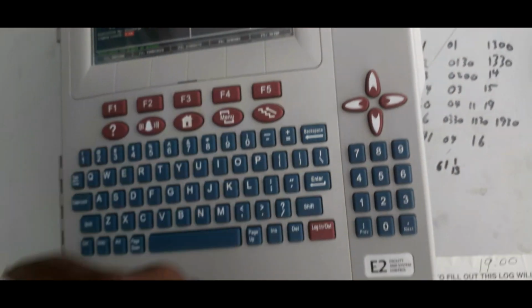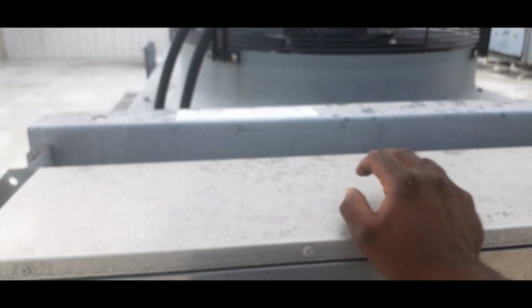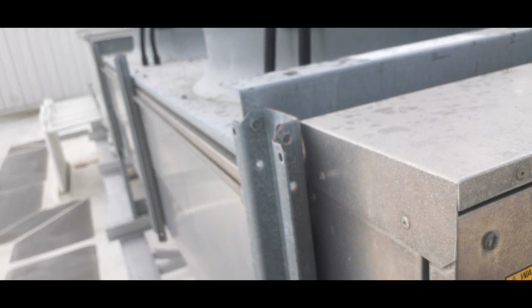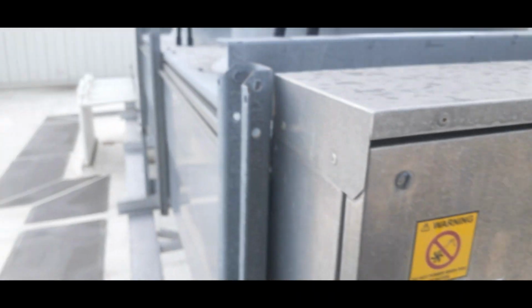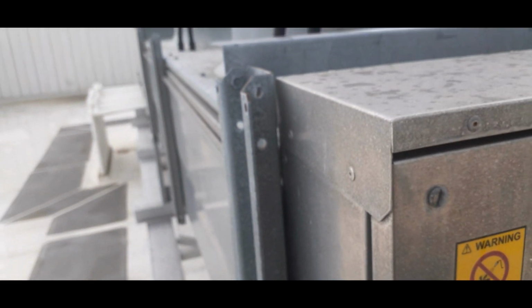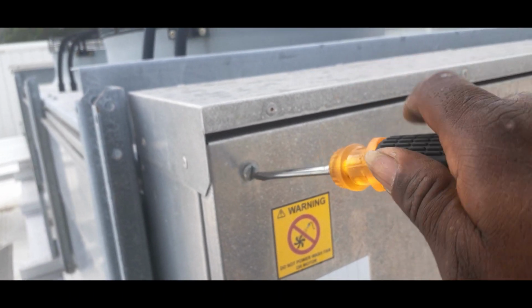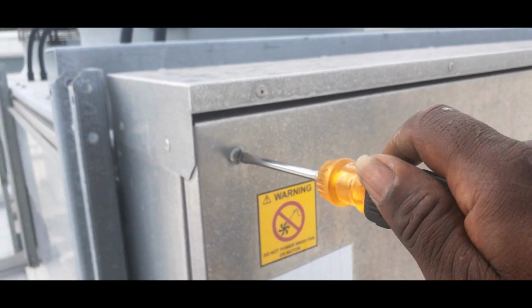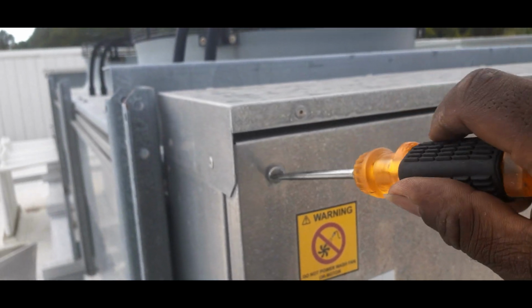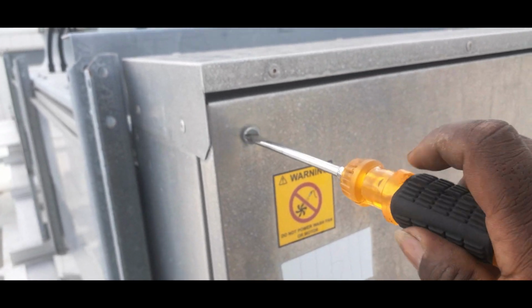One compressor came on. Let's check these condenser fans. So no condenser fans. Let's just cycle the power. Oops, I gotta get this open. Normally if you cycle the power on this, those fans should kick on. I might be going about this not in order, but we're trying to get to the same results. So it's all good, man.